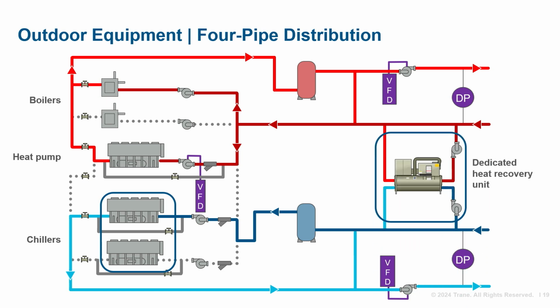In addition, a heat recovery chiller could be deployed between the distribution loops to further increase system efficiency. Notice, this unit is piped in the side stream position, drawing fluid off the return of both distribution streams. When it comes to heat recovery, there are several options available to explore. For a central plant, water-cooled machines will be used, so there is opportunity for heat recovery.